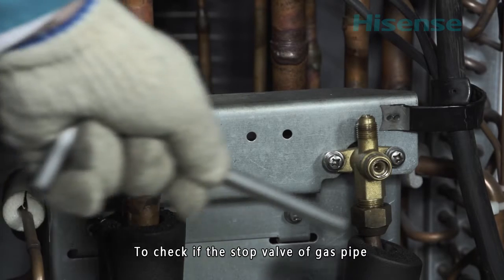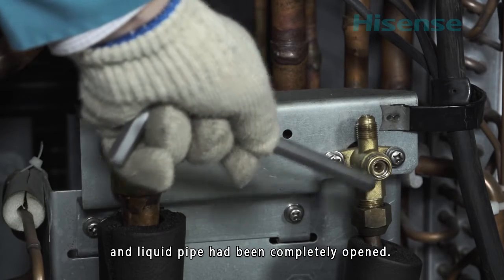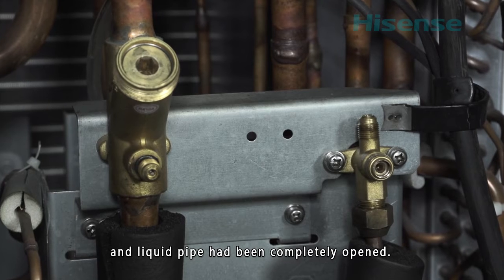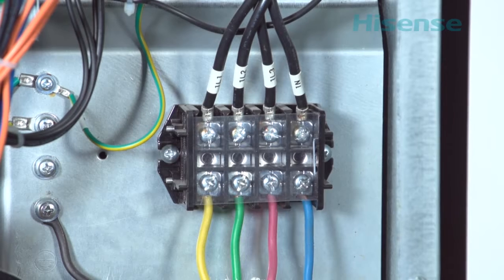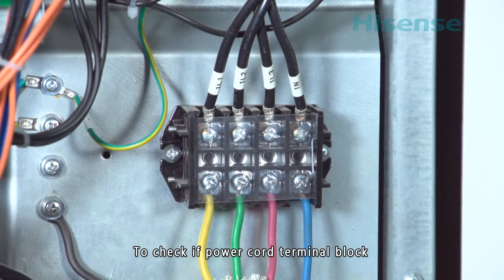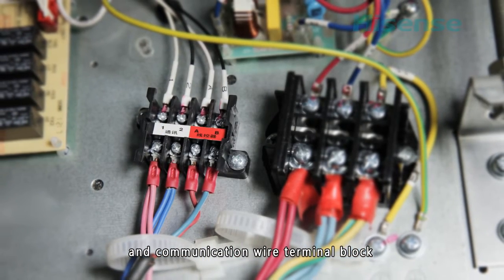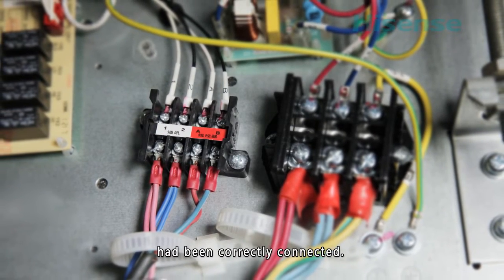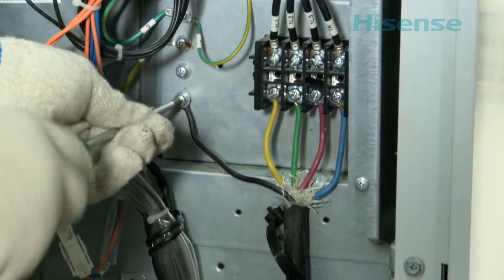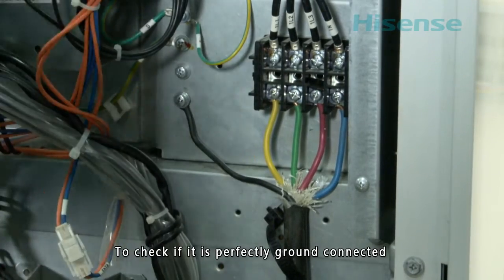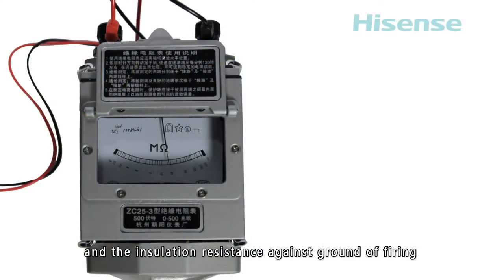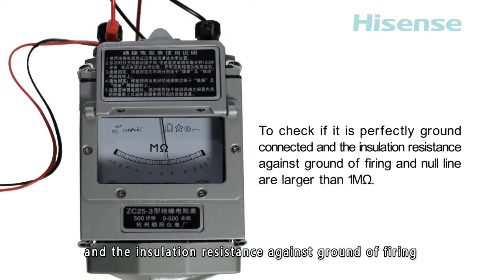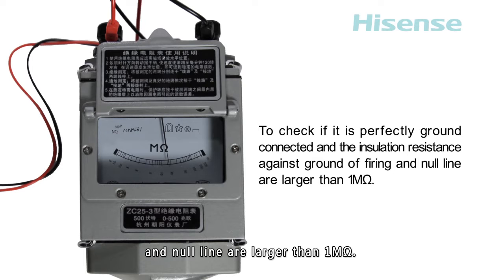9. To check if the stop valve of gas pipe and liquid pipe had been completely opened. 10. To check if power cord terminal block and communication wire terminal block had been correctly connected. 11. To check if it is perfectly ground connected and the insulation resistance against ground of firing and null line are larger than 1 megaohm.